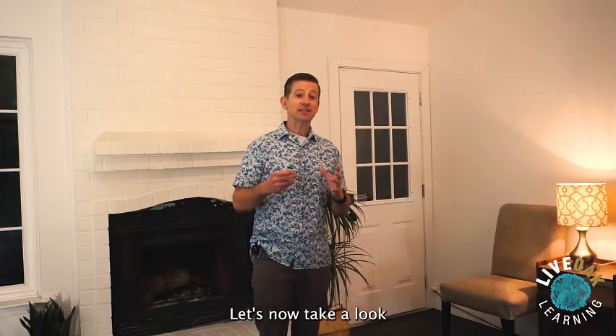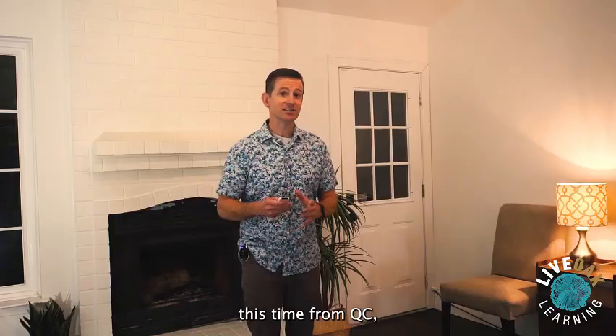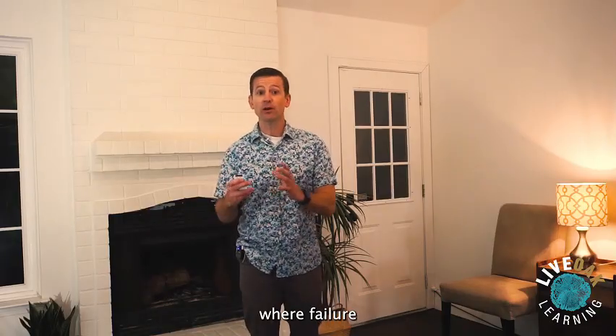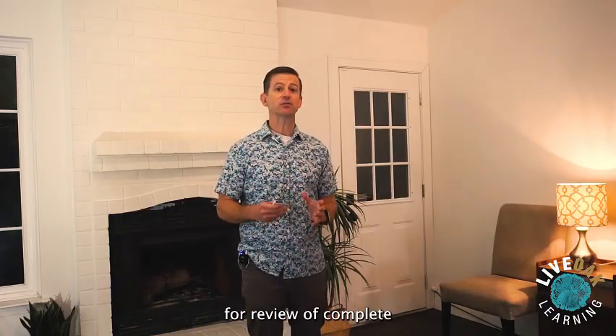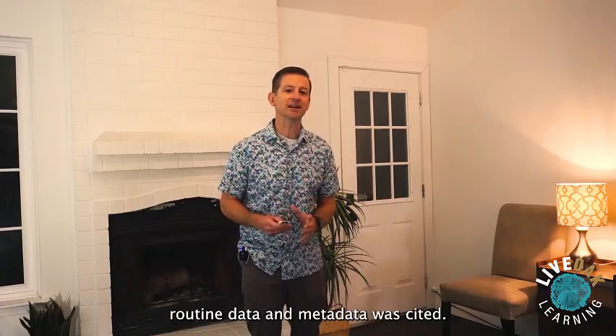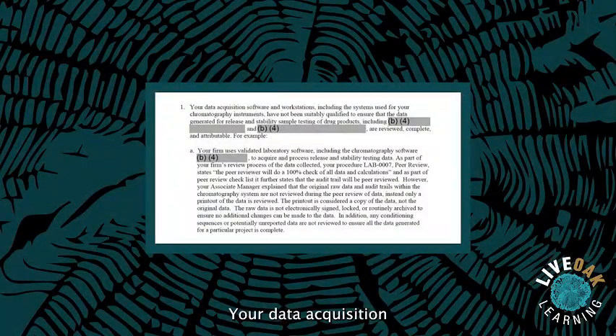Let's now take a look at another observation, this time from QC, where failure to establish a strategy for review of complete routine data and metadata was cited. Your data acquisition software and workstations, including the systems used for your chromatography instruments, have not been suitably qualified to ensure that the data generated for release and stability sample testing of drug products, including these things and these things, are reviewed, complete, and attributable.